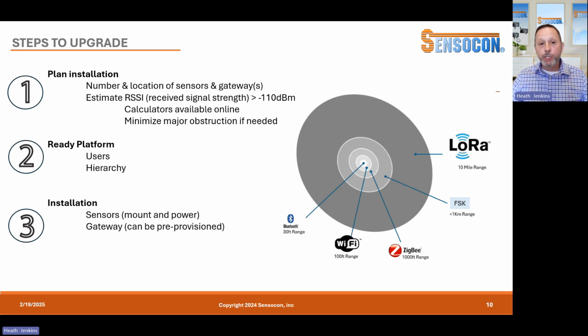For most instances, most plants, it's not going to be an issue. Minimize any major obstructions, huge steel sheets are tough on any wireless sensor. You could try it, but if you can minimize that by going up a floor level, height is wireless's best friend, so if that helps avoid obstructions, it's sometimes worthwhile.